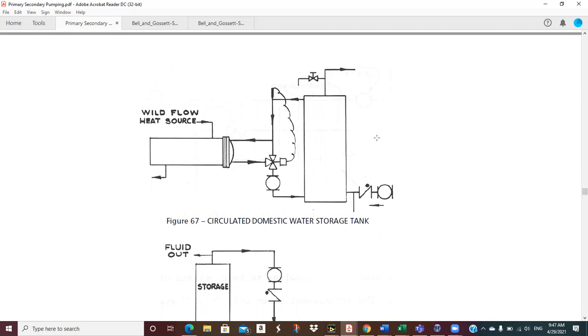whatever. But so here's our domestic water tank. It's not labeled, but this is our circulating pump that circulates out through the building to make sure that everybody has hot water close to them. So when you open a faucet, you don't have to wait for 10 minutes for the hot water to get to you. So this tank, maybe it's 180. You're going to be circulating 180-degree water around in a circle, and then everybody pulls off, and they've got 3 or 4 feet of pipe, which takes about 10 seconds, and all of a sudden you've got hot water.